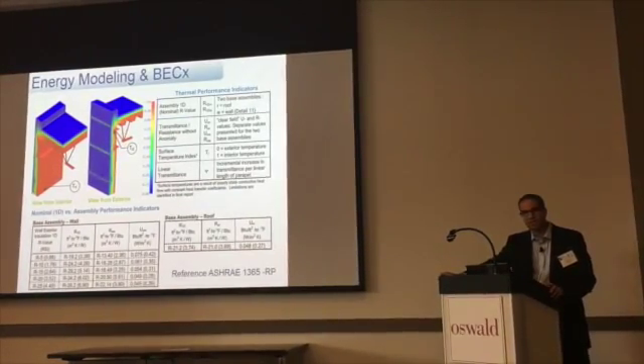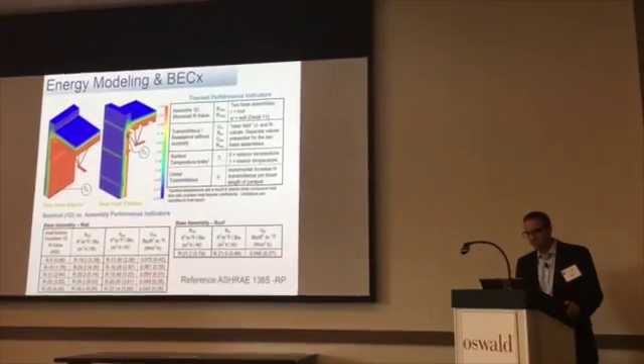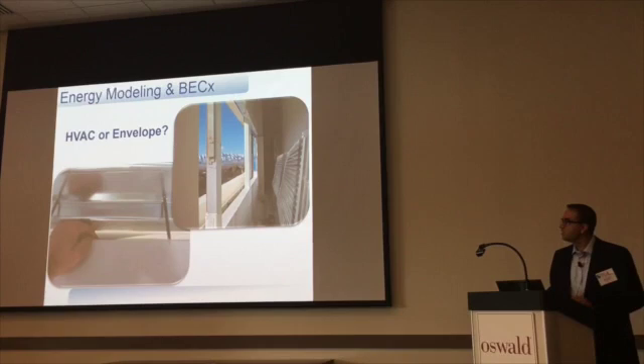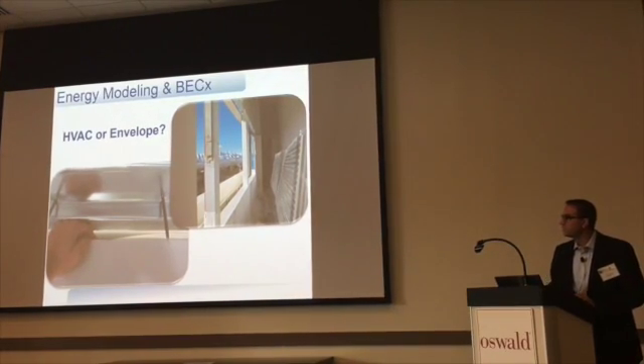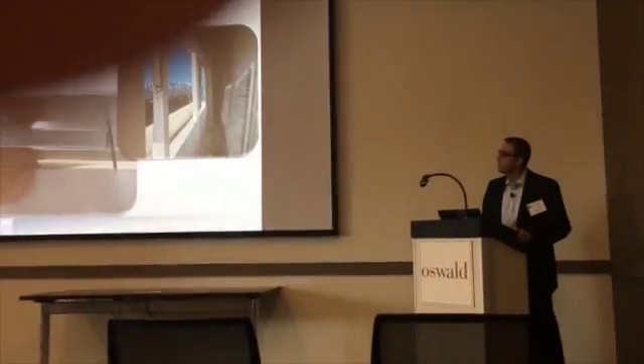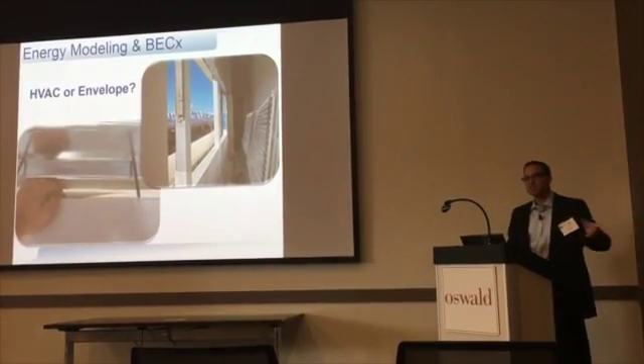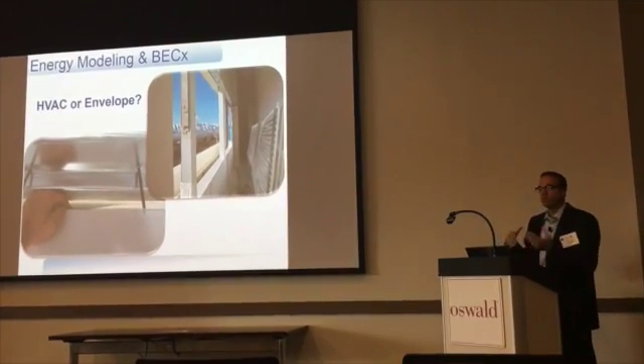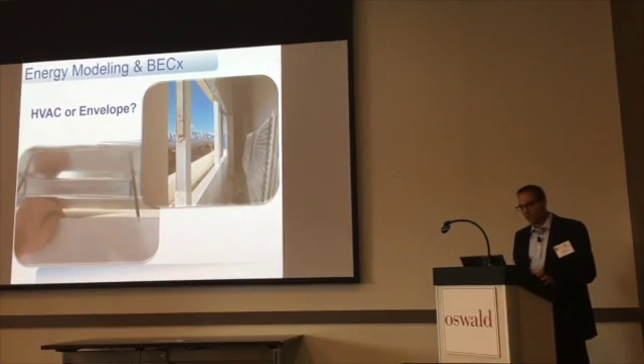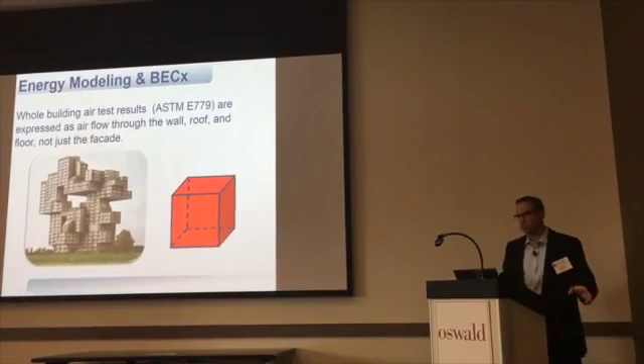ASHRAE's 1365 research survey went through common construction details and how we can improve them purely from a thermal perspective. We have a lot of projects where there's confusion over what is the boundary between inside and outside. On a project out west, we walked up and they were putting louvers in — roofing and waterproofing down on the floor, about ready to put a louver in. I looked up at the ceiling and everywhere there was a flute in the deck, you could put your hand through it. Where are you going to stop the air? You're not going to stop it at the louver — this was an air intake, essentially part of the shaft. They controlled the water with the roof membrane on the ground, but they didn't control the air leakage. You can hemorrhage air leakage around your filtration systems if you're not paying attention to having that continuous enclosure.